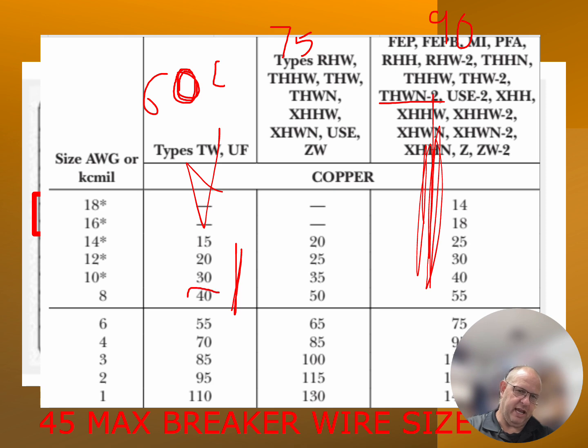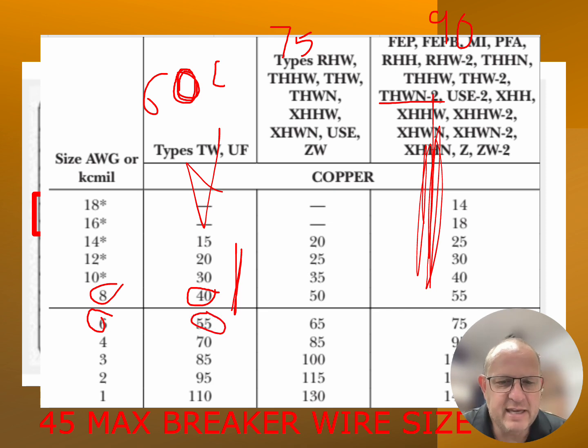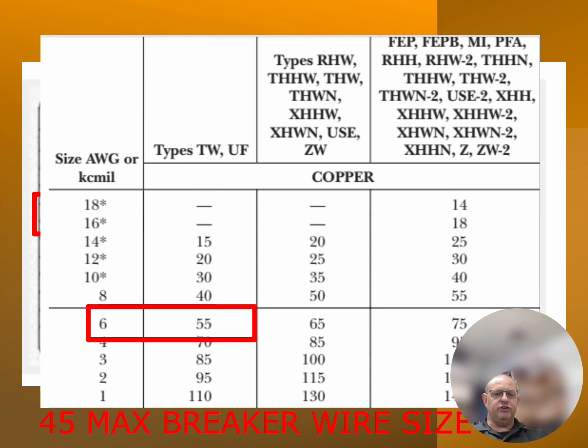Okay, can I put in a 40 amp wire on 8 gauge? And the answer to that is no. I have a 45 amp breaker in here. The 8 gauge wire can only handle 40 amps at 60 degrees Celsius. So I can't use an 8 gauge wire. So I will step it up to the next wire. I will find out that the 6 gauge wire can take up to 55 amps. Can I use a 6 gauge wire with a 45 amp breaker? And the answer to that question is absolutely yes. So I want to choose the 6 gauge wire at 55 amps.